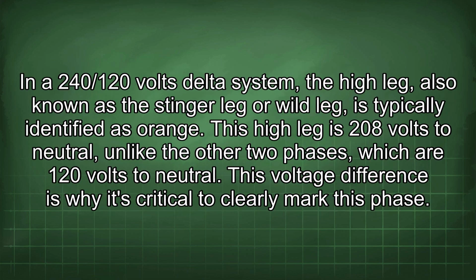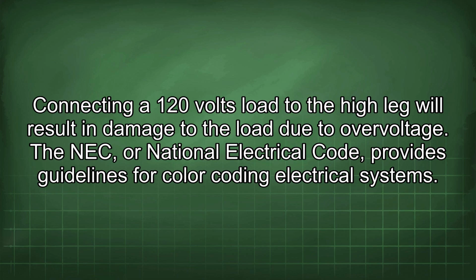In a 240/120 volts delta system, the high leg, also known as the stinger leg or wild leg, is typically identified as orange. This high leg is 208 volts to neutral, unlike the other two phases, which are 120 volts to neutral. This voltage difference is why it's critical to clearly mark this phase. Connecting a 120 volts load to the high leg will result in damage to the load due to overvoltage.